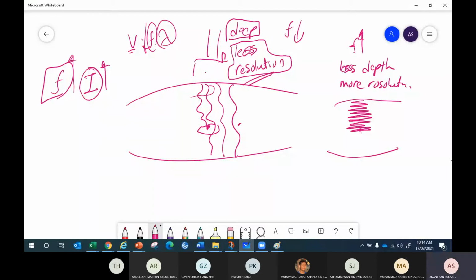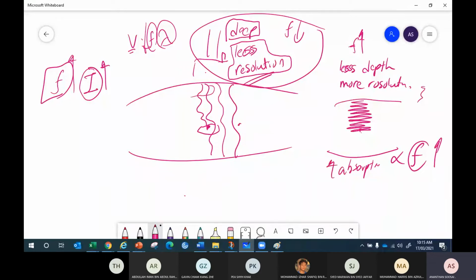Remember this. Low frequency, you can go deeper, but less resolution, less information about the body, so you need to scan a few times. Higher frequency, you get more resolution, better scanning, better searching. A smooth stone can also be detected by using high frequency, but you can't go deep because absorption is significant. Absorption is found to be proportional to the frequency of the sound. The higher the frequency, the greater the absorption.